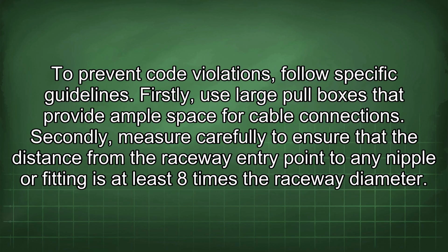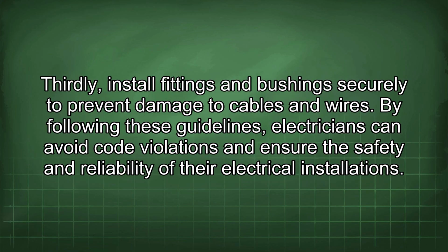To prevent code violations, follow specific guidelines. Firstly, use large pull boxes that provide ample space for cable connections. Secondly, measure carefully to ensure that the distance from the raceway entry point to any nipple or fitting is at least 8 times the raceway diameter. Thirdly, install fittings and bushings securely to prevent damage to cables and wires. By following these guidelines, electricians can avoid code violations and ensure the safety and reliability of their electrical installations.